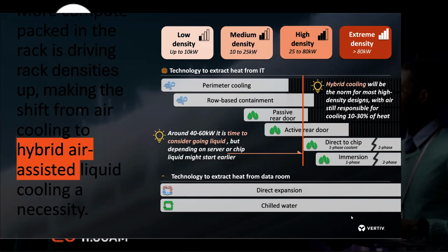So at every point in time, the cooling solution for this kilowatts of cooling or the density of heat load changes. Between 10 kilowatts to maybe 80 kilowatts, we're still good with perimeter cooling, row-based cooling, and maybe passive rear door cooling. But as the heat begins to increase from 80 kilowatts and above, we have to move to direct-to-chip cooling and immersion cooling, like we saw in the slides before.